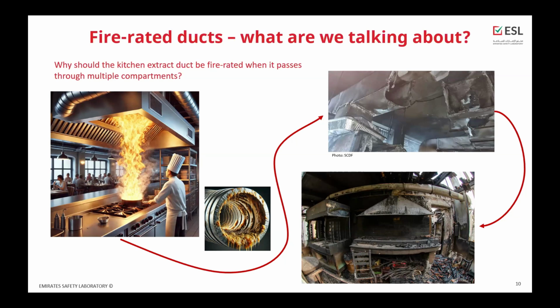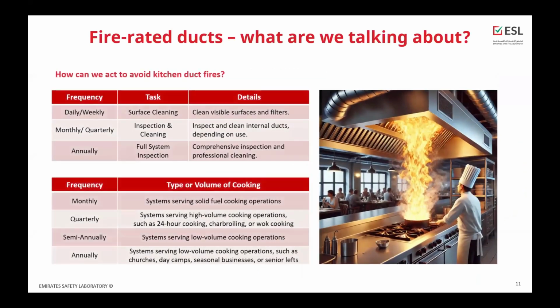If the duct is made from the wrong material, not fire rated, it may melt, for example if it is made from aluminium, and spread the fire to other parts of the kitchen or other parts of the building, causing the total loss of the kitchen or even the whole restaurant. Sometimes even the rest of the building may be affected if the fire protection is not done correctly. So what can we do, how can we avoid these kitchen fires?